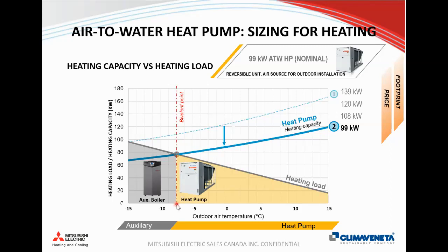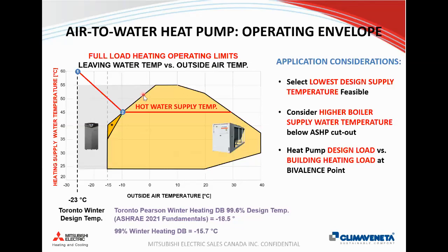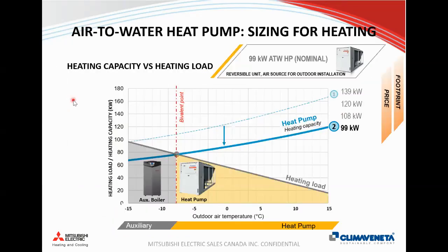So this would be a system where you're happy with using about a 48, 49 degree supply temperature from the heat pump. The supply temperature that you select when selecting a machine will dictate the ambient temperature that you're using it down to. Usually 45C down to minus 10 is a good balance between having a broad range where you can hit that temperature consistently versus having a water temperature that's high enough to get good heat transfer through typical heat emitters.